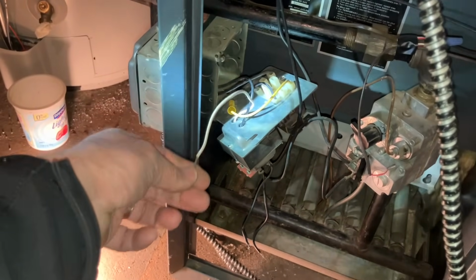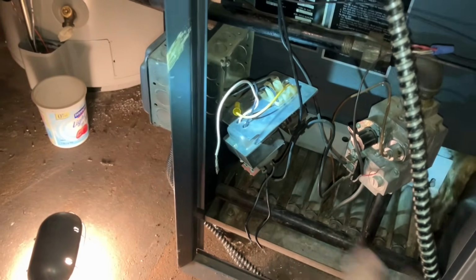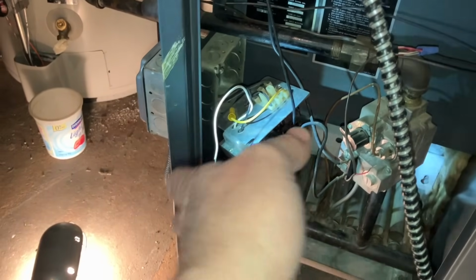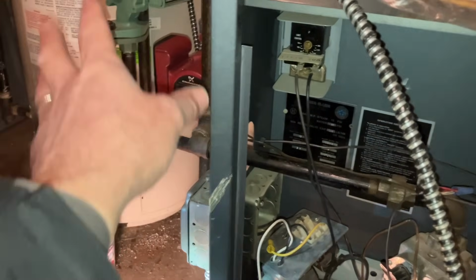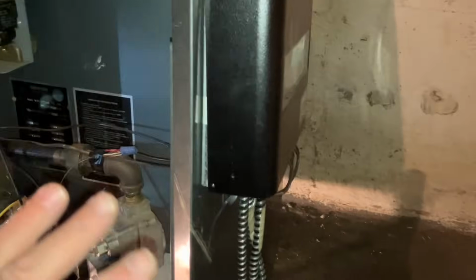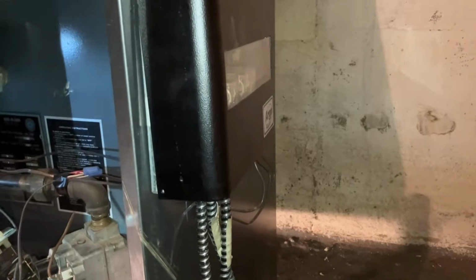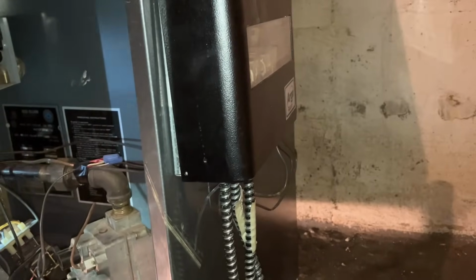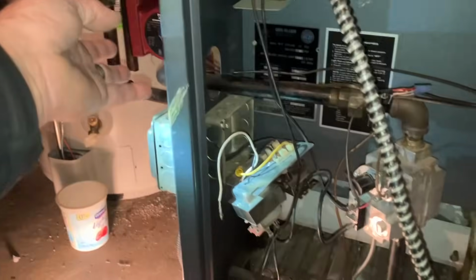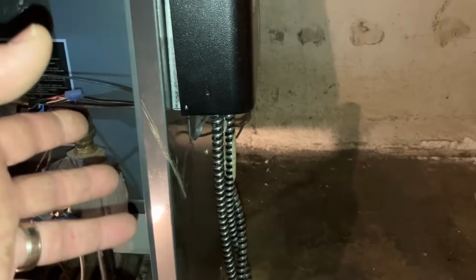Either it got disconnected or what have you, but it does kind of make sense that you were taking the cover on and off, and it corresponded to the system turning on and off. But let's explain how things are. You have two circulators that are getting power exclusively from the two-zone switching relay that's here. The switching relay gets constant power. It gets a signal from the thermostat to turn on. When it does, that 24 volts closes that relay and sends 110 volts from the line into the load. So if zone 1 is on, zone 1 load is getting power from line, and then that circulator runs.